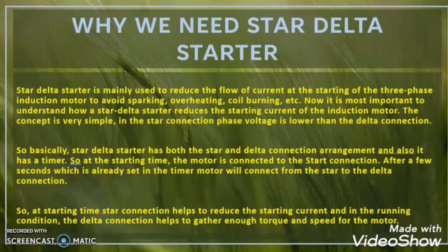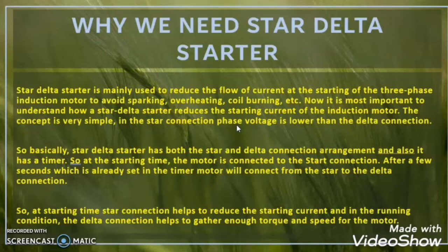As the inrush current is temporary in the induction motor — once the motor reaches 80% of its rated speed, the inrush current will vanish. At that point, the star delta starter gives the full rated voltage and rated current to the induction motor to achieve its required torque and speed. So the concept is clear: give reduced voltage and current during starting, then switch to rated values once the motor reaches 80% of rated speed.